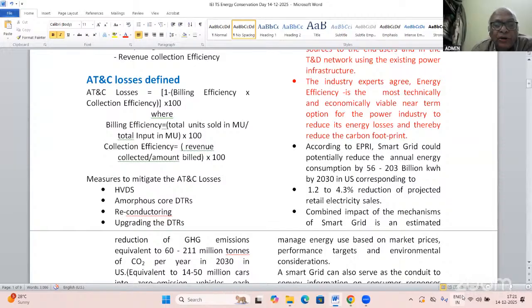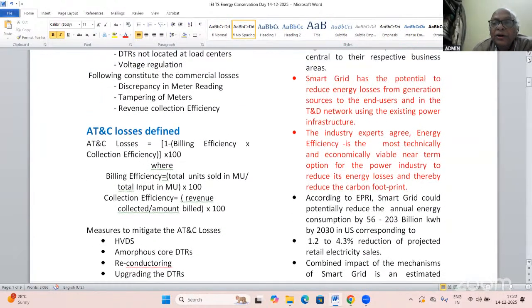Then there are amorphous core transformers for loss reduction in transformers and low load losses, and reconductoring and upgrading the DTRs. These are the mitigation measures.